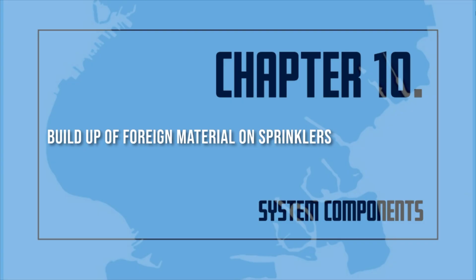Buildup of foreign material on sprinklers. Sometimes conditions exist which cause a buildup of foreign material on sprinkler heads. This may prevent the sprinkler head from working properly. This buildup is commonly called loading. The buildup of foreign material insulates the sprinkler head. This buildup prevents the sprinkler from opening at the desired temperature. If the buildup is hard, it may prevent the sprinkler from opening. Replace loaded sprinkler heads with new sprinkler heads rather than attempting to clean them. If the deposits are hard, attempts to clean the heads are likely to damage them.